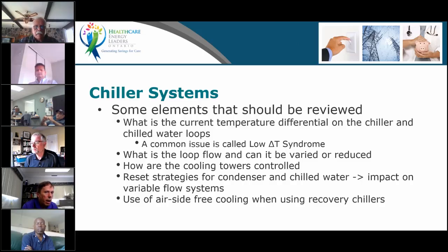The type of reset: are you always keeping the same set point for your cooling tower? Is your cooling tower set point realistic? Some people put 19 degrees. I want 19 Celsius as my return. They know it's never going to be achieved most of the time in the summer. So they also have VFDs on those fans, and the fans never catch up. So there's something called wet bulb reset for a cooling tower. So look at different reset strategies, but look at the total impact of your reset strategy.